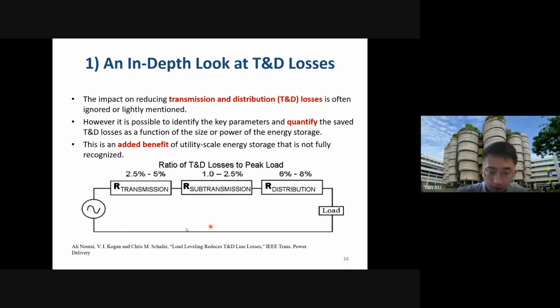So according to this paper, you can see the ratio of the transmission and distribution loss during the peak load is very big. Our transmission network is around 2.5 to 5%. Sub-transmission network is 1 to 2.5%, and distribution network is even higher because the voltage is lower, so the current is higher. It is around 6 to 8%.